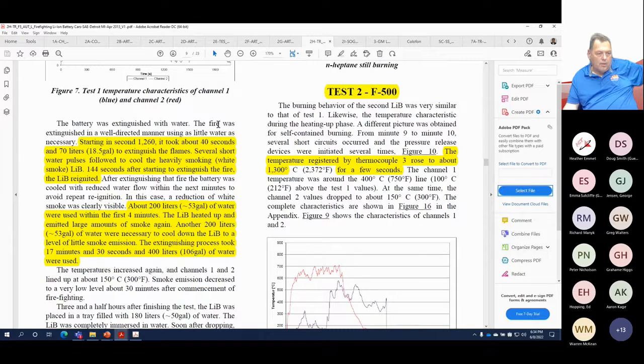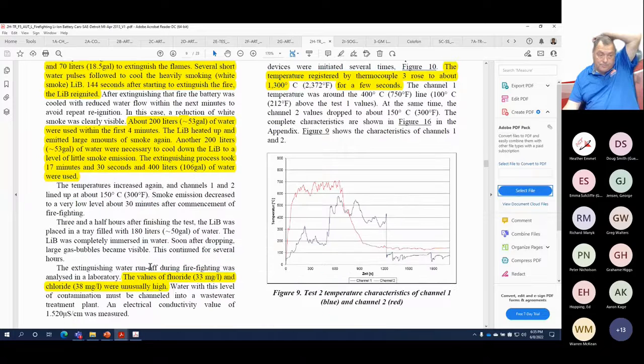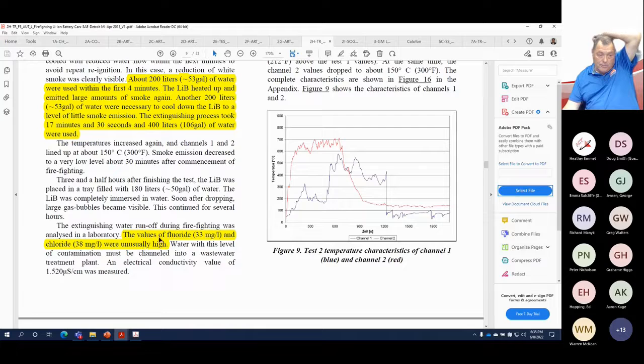The battery was extinguished with water. So here it took 40 seconds and 70 liters to extinguish the flames. Several short water pulses followed to cool the heavy white smoke. However, 144 seconds to 2 minutes after starting the extinguishment, the lithium-ion battery reignited. So now another 200 liters of water were used within the first 4 minutes. The lithium-ion battery heated up again, emitting large amounts of smoke. Another 200 liters were necessary to cool it down to the level to stop the smoke. The extinguishment took 17 minutes, 30 seconds, and 400 liters of water were used. Here they're coming back, just saying the values of the fluorides and chlorides seemed unusually high.